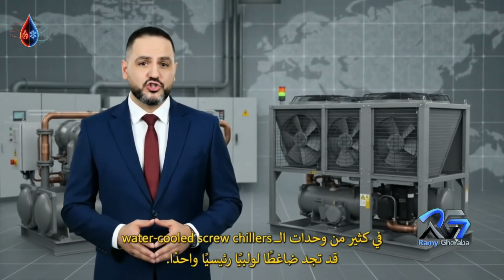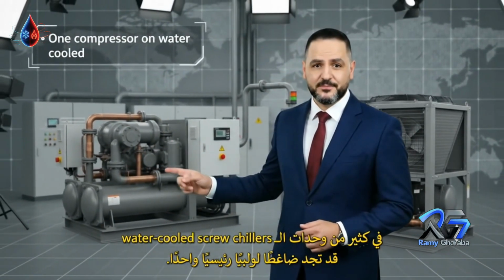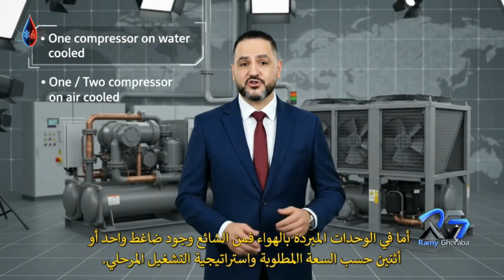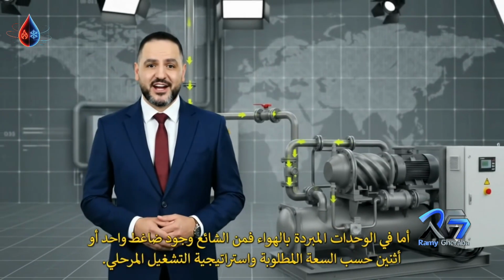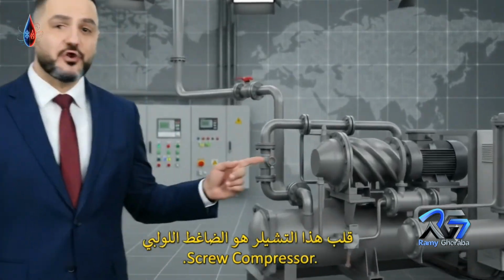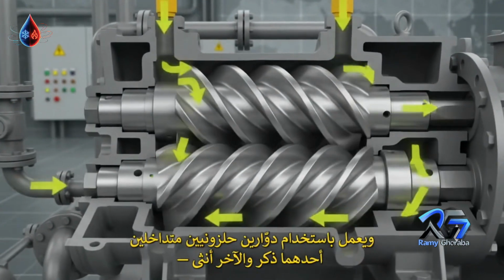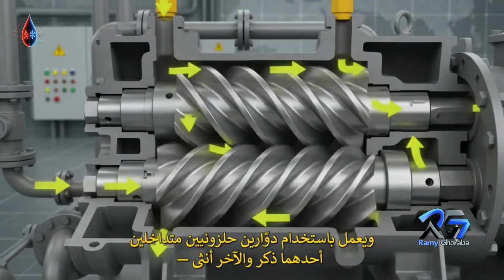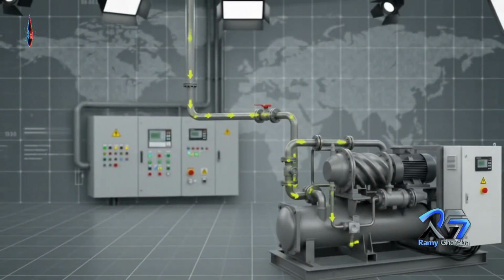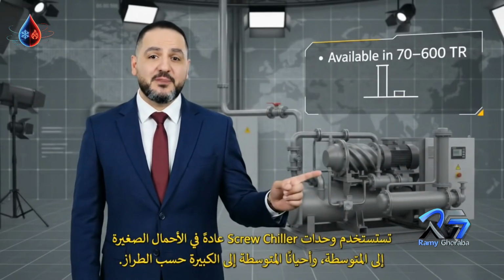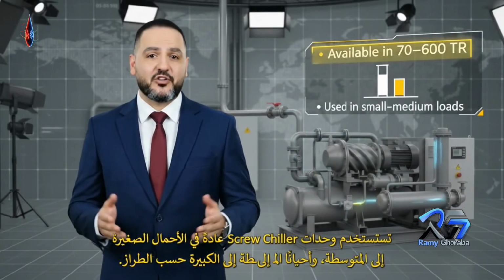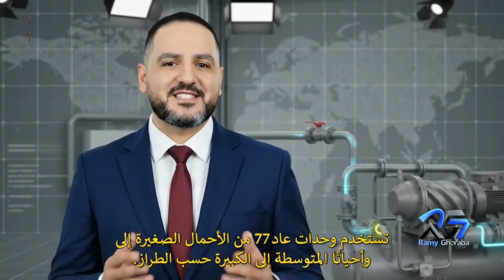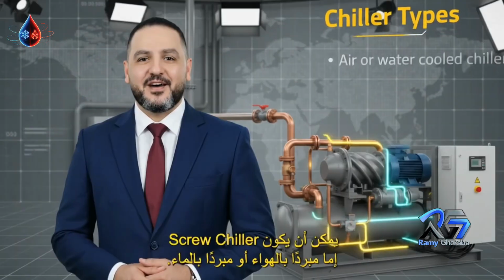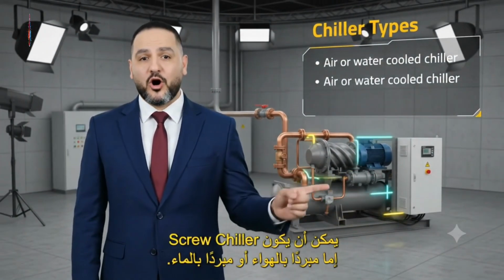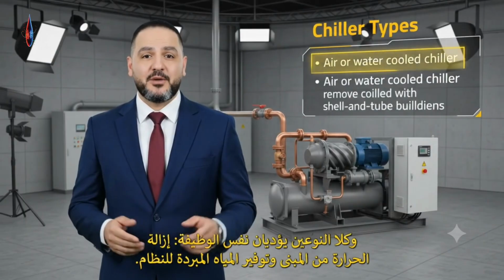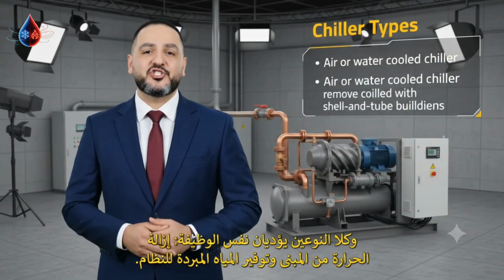In many water-cooled screw chillers, you may find one main screw compressor. In air-cooled units, one or two compressors are common, depending on the required capacity and strategy. The heart of this chiller is the screw compressor. It uses two meshing helical rotors, a male rotor and a female rotor, to compress the refrigerant continuously and smoothly. Screw chillers are commonly used in small to medium, often medium to large applications depending on the model. A practical range is around 70 to 600 tons of refrigeration. A screw chiller can be either air-cooled or water-cooled. Both versions do the same job, removing heat from the building and delivering chilled water to the system.